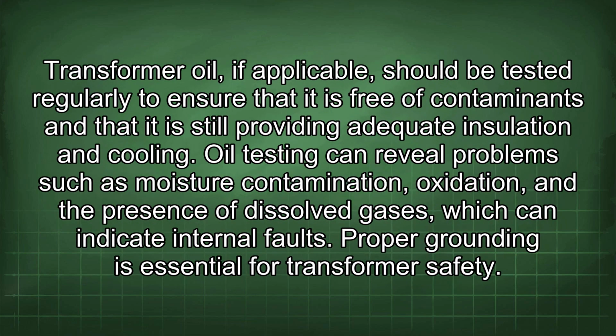Transformer oil, if applicable, should be tested regularly to ensure that it is free of contaminants and that it is still providing adequate insulation and cooling. Oil testing can reveal problems such as moisture contamination, oxidation, and the presence of dissolved gases, which can indicate internal faults. Proper grounding is essential for transformer safety.